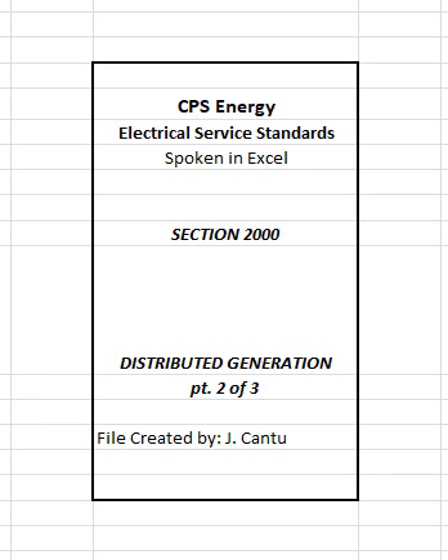I. Rapid shutdown of PV systems. Rapid shutdown shall be required in accordance with the NEC and shall be included in the design with proper labeling. Refer to Figures 2002 through 2006. J. Grounding of PV systems. Grounding shall be as permitted by the NEC and in accordance with Figures 2002 and 2004. K. PV system conductors in attic spaces. Where PV system DC conductors are to be installed in attic spaces, conductors shall be installed in approved metal raceways/conduits in accordance with the NEC and other applicable codes. Where PV system AC conductors are to be installed in attic spaces, the conductors shall be installed in approved raceways/conduits with labels denoting PV AC conductors.